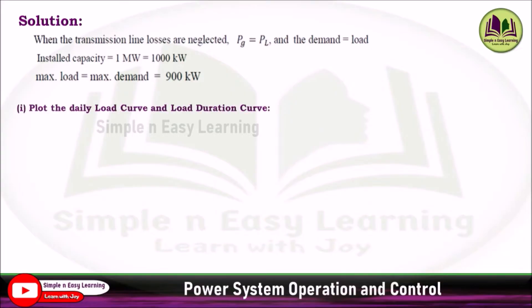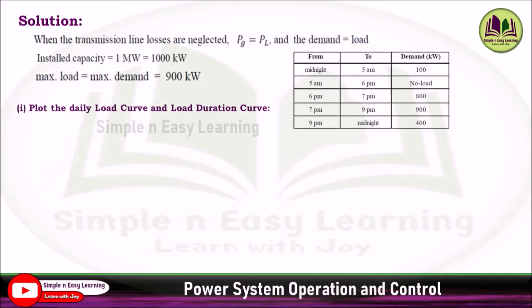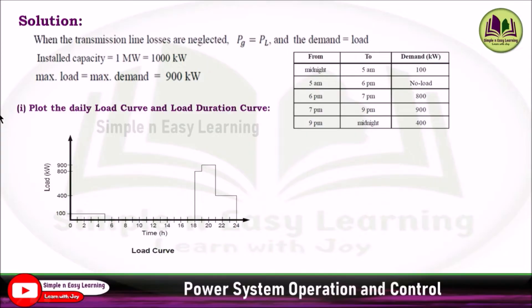First, plot the daily load curve and load duration curve. From the given table you can plot the load curve. The maximum value is 900 kilowatt. Take a scale on the y-axis up to 900, and on the x-axis the time represents one day, midnight to midnight, so 0 to 24 hours. From midnight to 5 a.m. it is 100 kilowatt, so 0 to 5 it is 100 kilowatt.